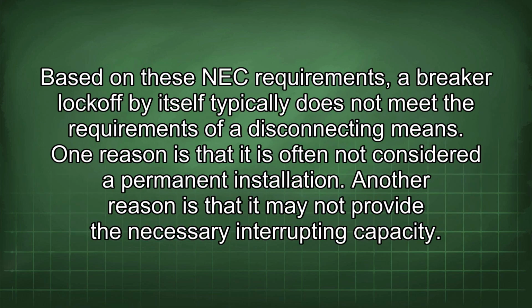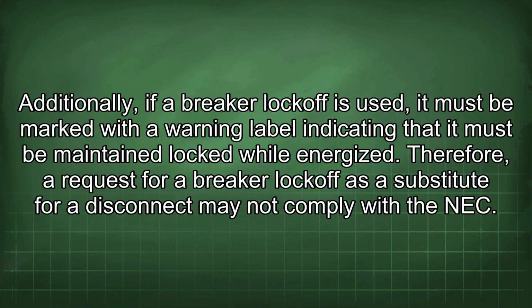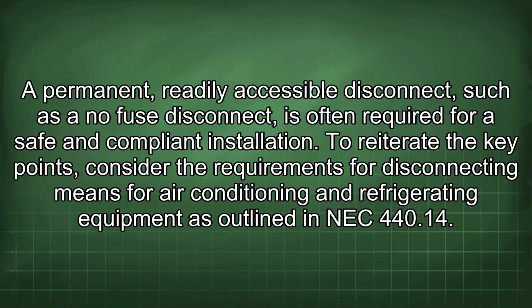Based on these NEC requirements, the breaker lockoff by itself typically does not meet the requirements of a disconnecting means. One reason is that it is often not considered a permanent installation. Another reason is that it may not provide the necessary interrupting capacity. Additionally, if a breaker lockoff is used, it must be marked with a warning label indicating that it must be maintained locked while energized. Therefore, a request for a breaker lockoff as a substitute for a disconnect may not comply with the NEC. A permanent, readily accessible disconnect, such as a non-fused disconnect, is often required for a safe and compliant installation.